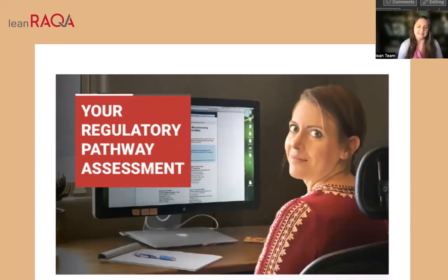And what is a regulatory pathway assessment? Well, a regulatory pathway assessment is a formal document that basically defines your regulatory strategy. It takes a look at what your classifications are, who your competitors are, and some important product features you need to be mindful of. If we complete this for you, we obviously put recommended next steps and risks to submission, or maybe risks if you're on a cutting edge novel technology. It's really just a nice formal report to get started.